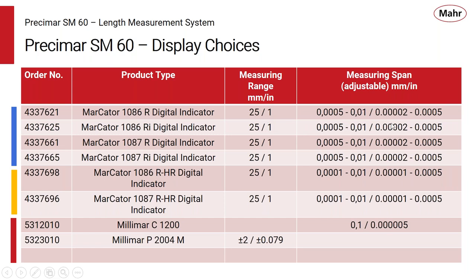And these can get down to basically 20 millionths of an inch. They're selectable resolutions, so you can dial in the resolution that best matches the tolerance that you're trying to measure to. So these are some great measuring options. A little bit better, the yellow ones here are our high resolution digital indicators, either the 1086 or 1087. These go down to a 10 millionth resolution. So now you can have 1 inch of travel with 10 millionths resolution from a digital indicator. So now we're really getting the performance out of the SM60.